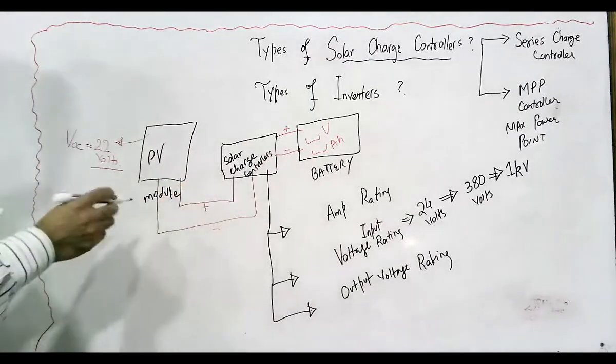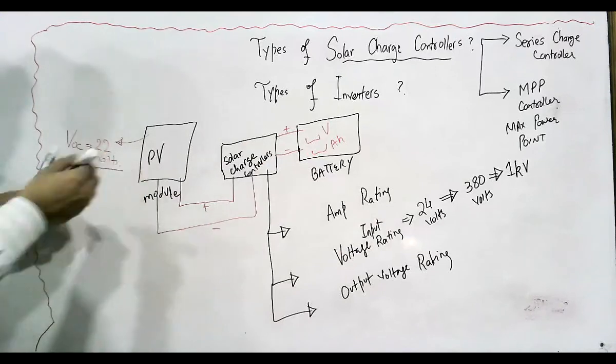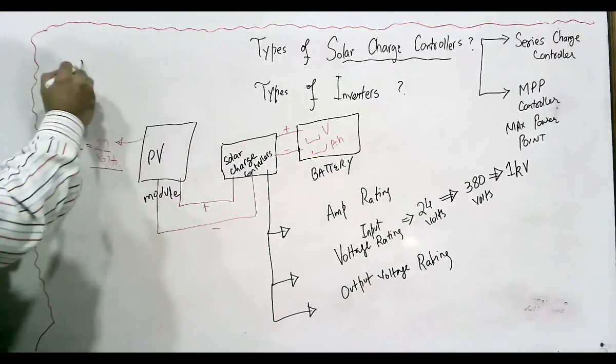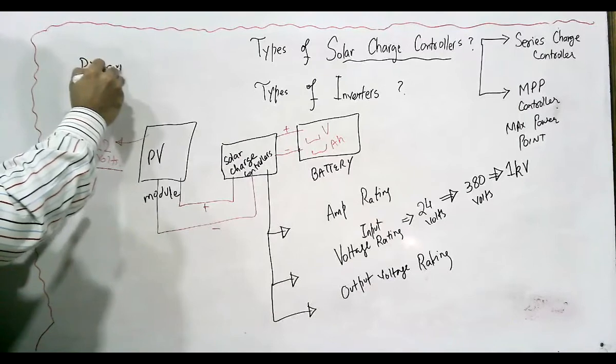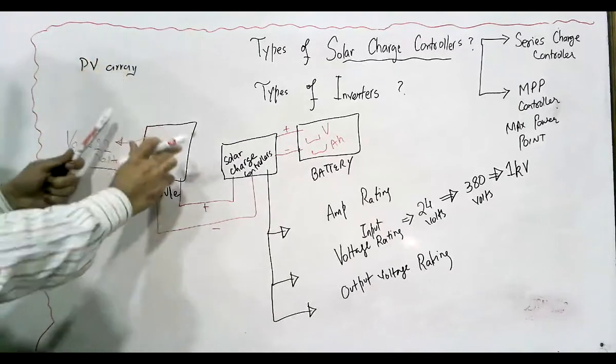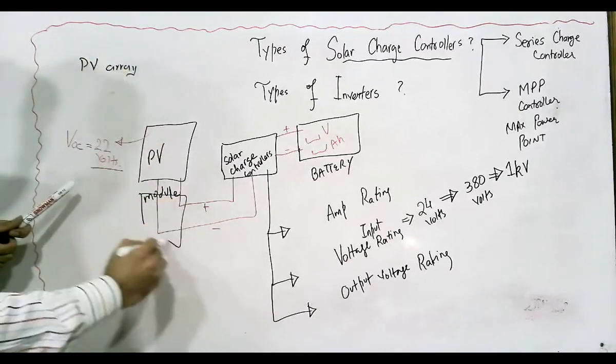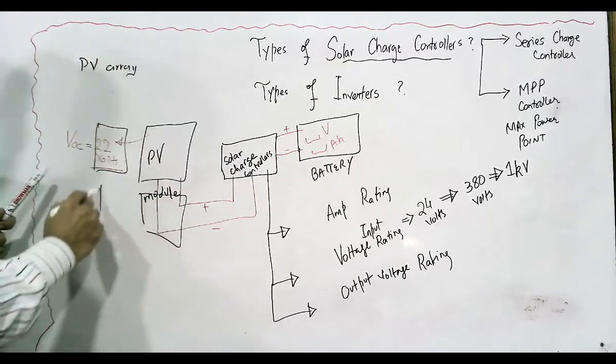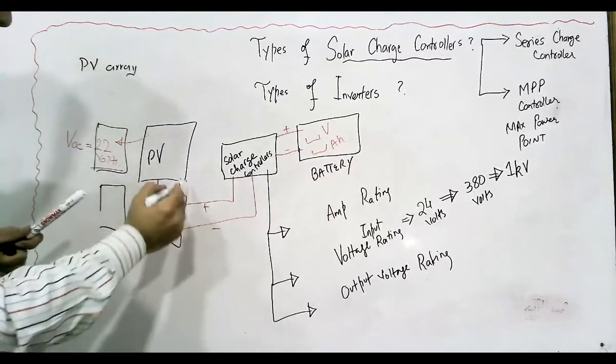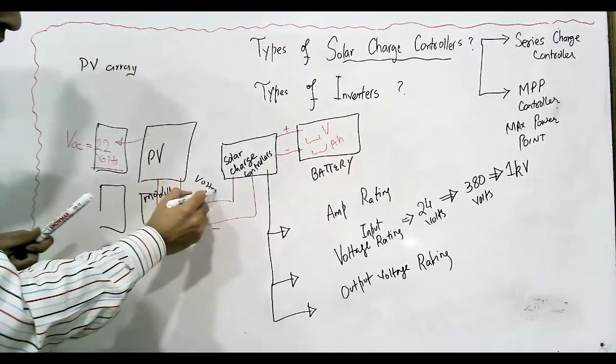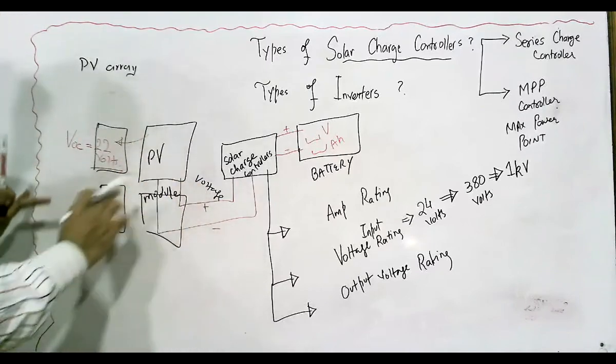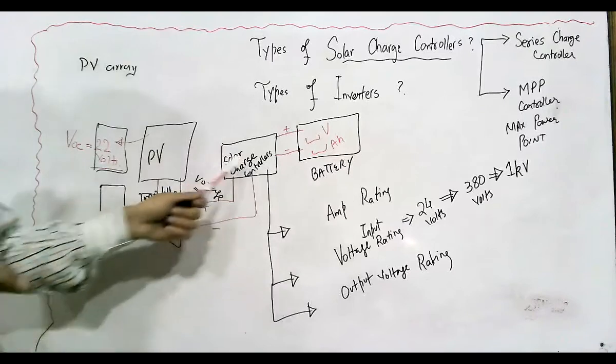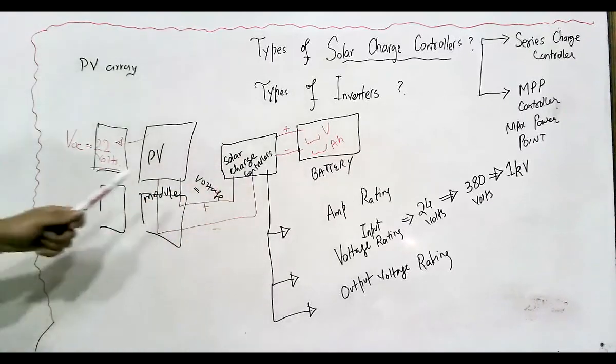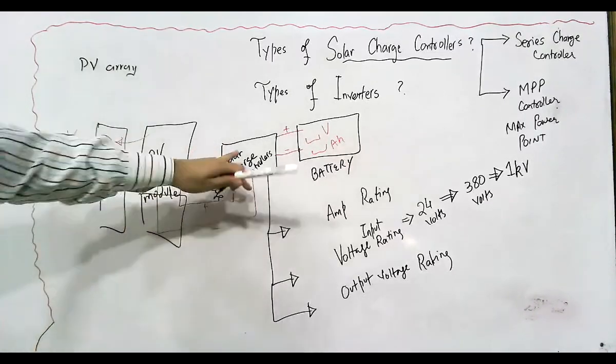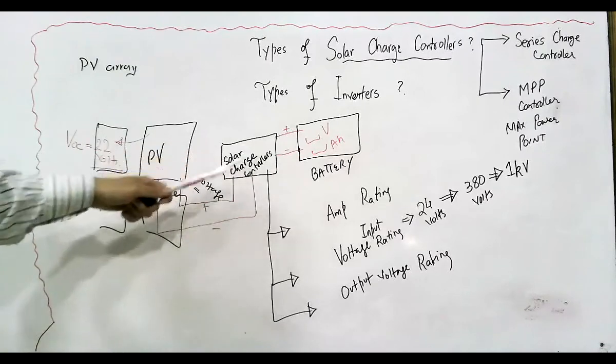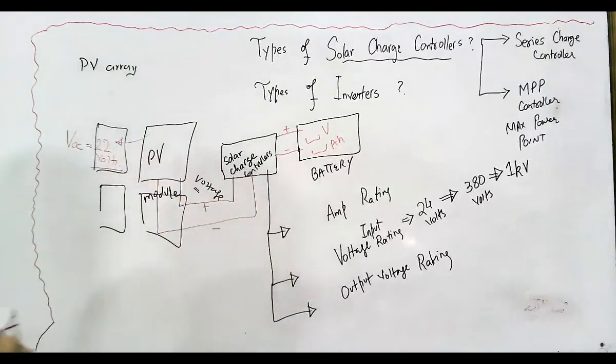Now, if you have more than one PV array module, you have a type of PV array with series or parallel combinations of PV modules. In that case, whatever the voltage of that PV array, your battery charger must be able to handle that voltage. This is how you decide the input voltage rating of the solar charge controller.